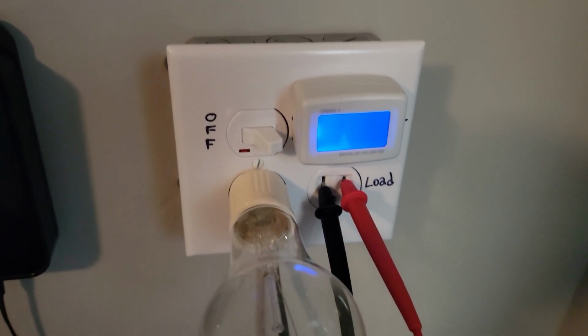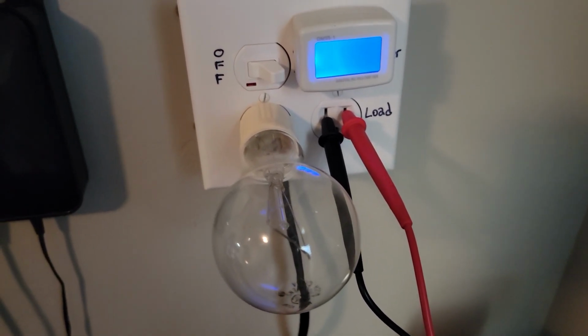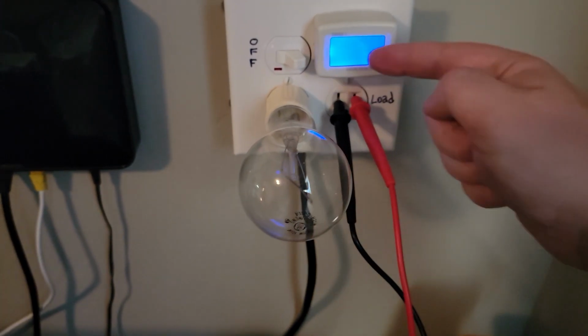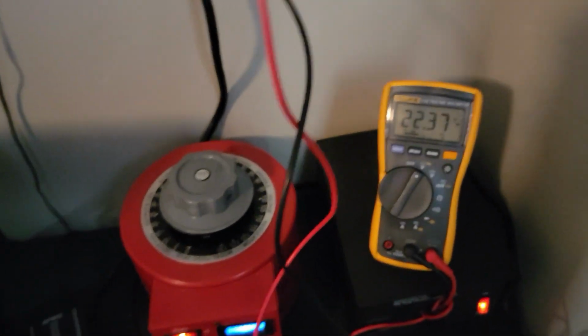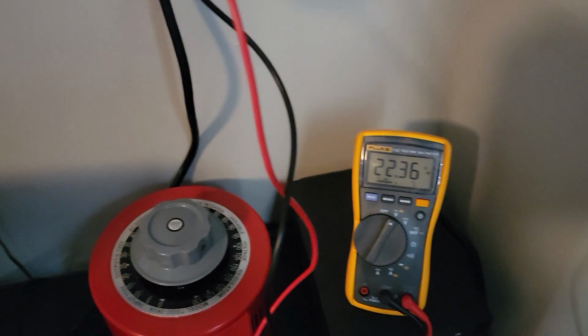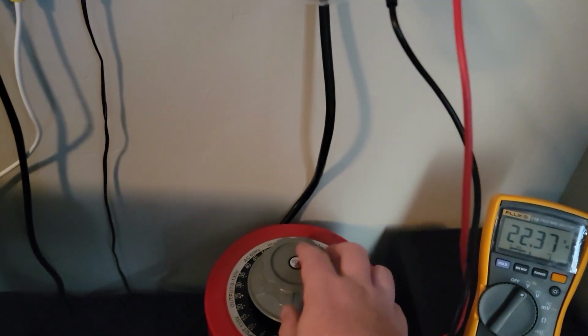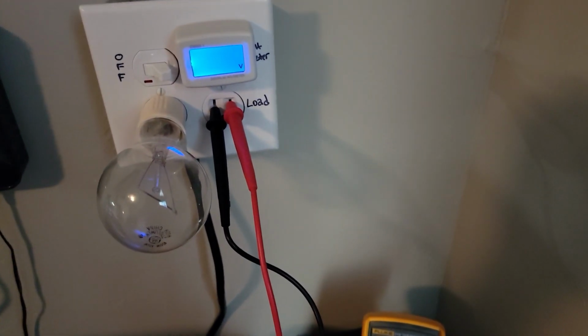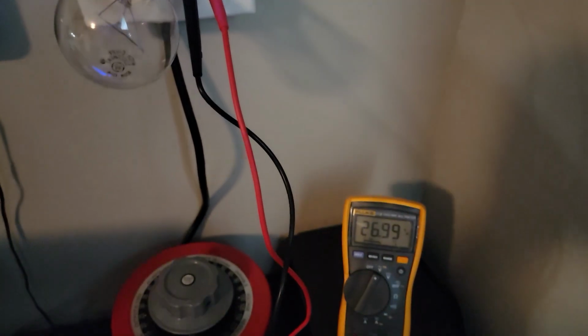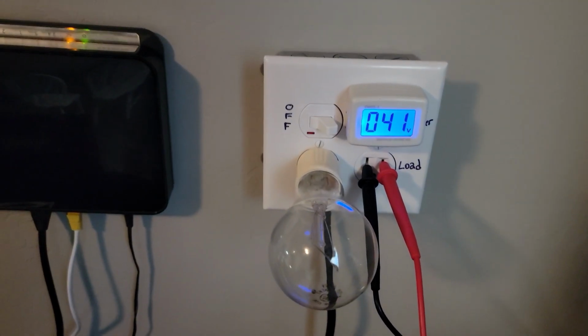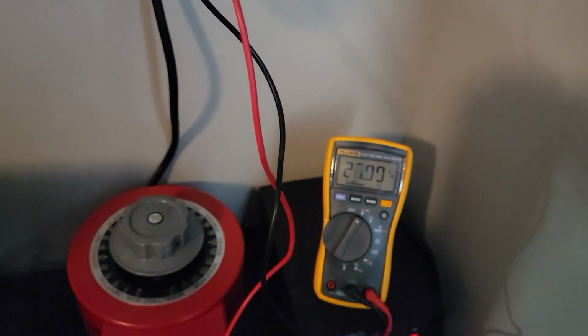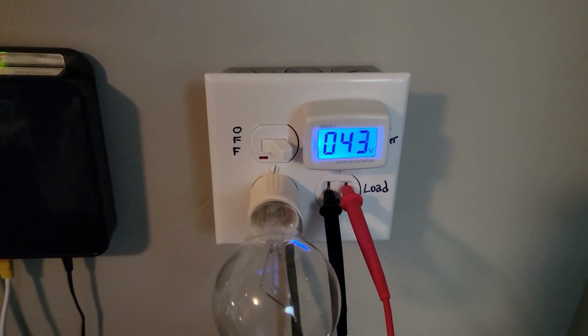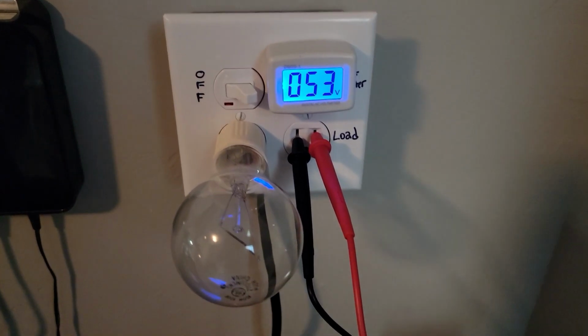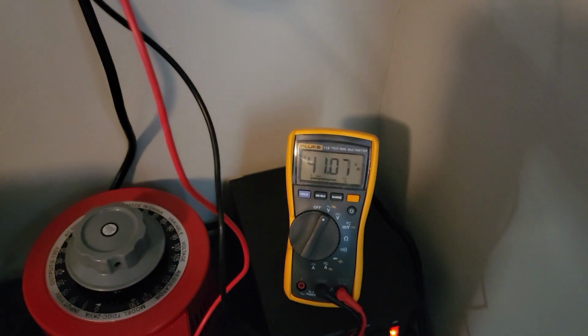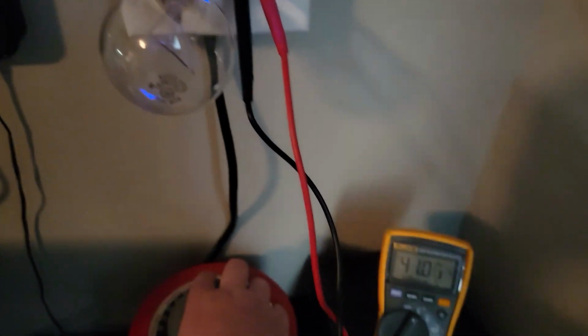Maybe we're around 10 volts or so. Starting to get power. That AC voltmeter is not picking up anything, but my Fluke meter is starting to pick up 22 volts AC. Picks up around 40, 41. Fluke meter is saying 26. Might just be too low to detect. Either that or it's just way off. 41, 53. It looks like it's just way off.